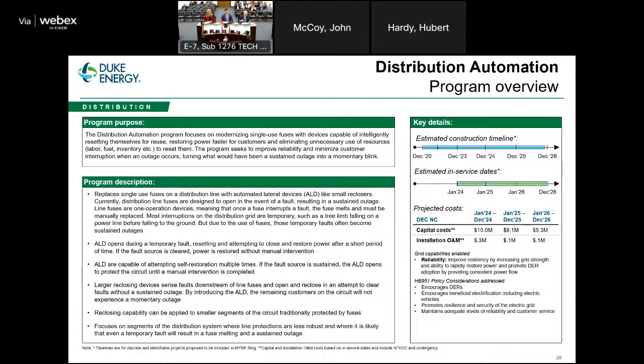These devices are even more sophisticated than that. If they see a temporary fault, they open, and after a prescribed time frame, they close back in automatically. If the fault was truly temporary, power is restored and customers only see a momentary blink instead of a sustained outage. Reliability is one of our four critical grid capabilities, and this work specifically addresses that.